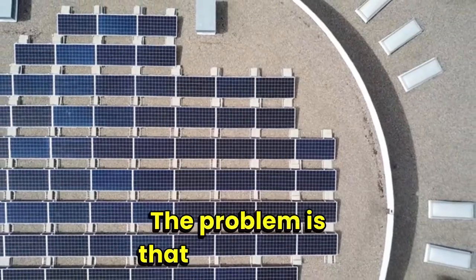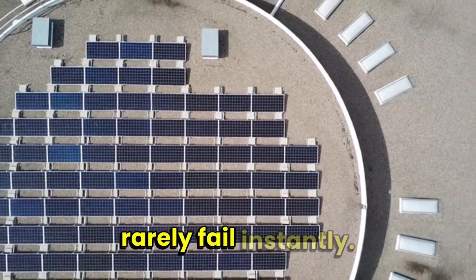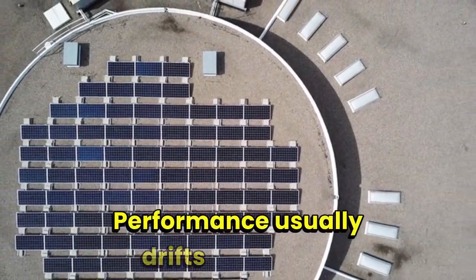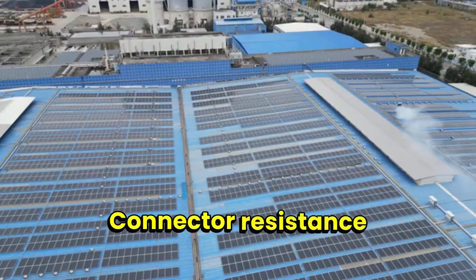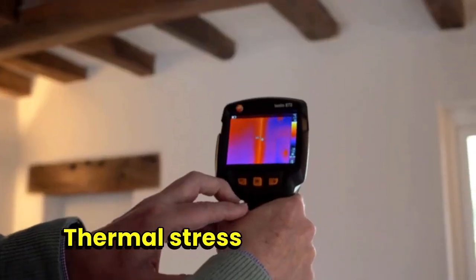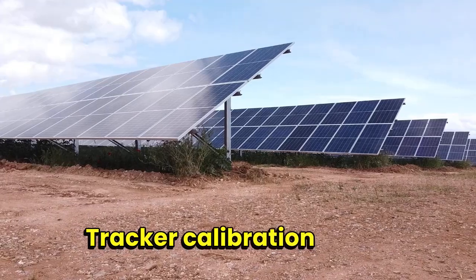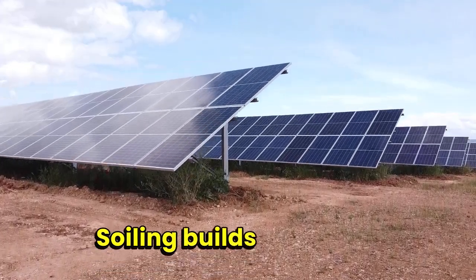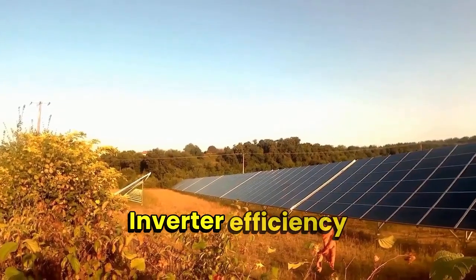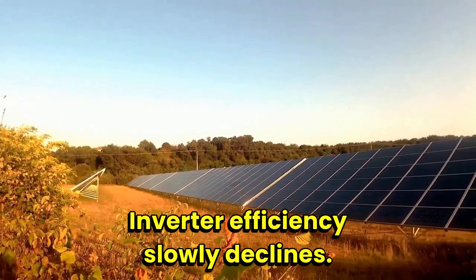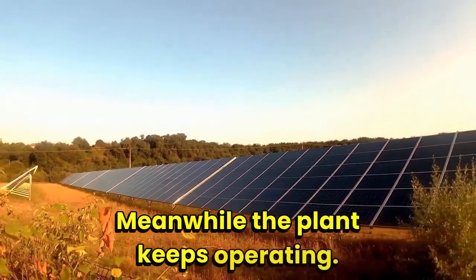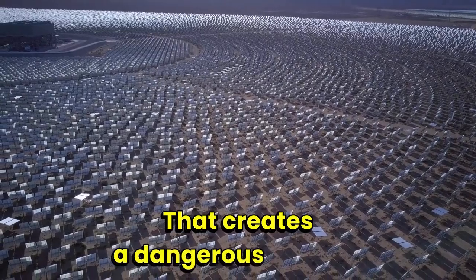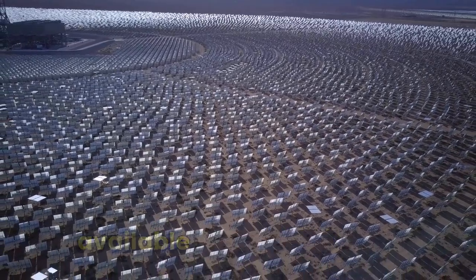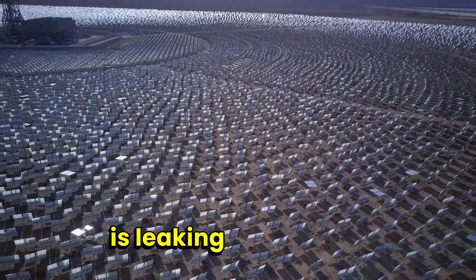The problem is that solar assets rarely fail instantly. Performance usually drifts gradually. Connector resistance increases. Thermal stress accumulates. Tracker calibration drifts. Soiling builds unevenly. Inverter efficiency slowly declines. Meanwhile, the plant keeps operating. That creates a dangerous illusion. The site appears available, but performance is leaking constantly.